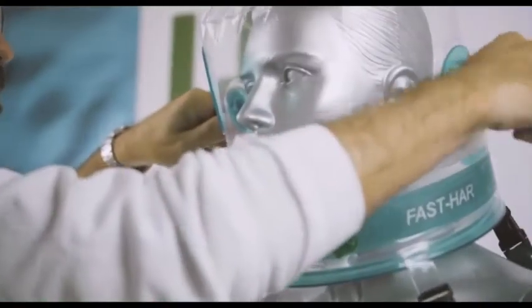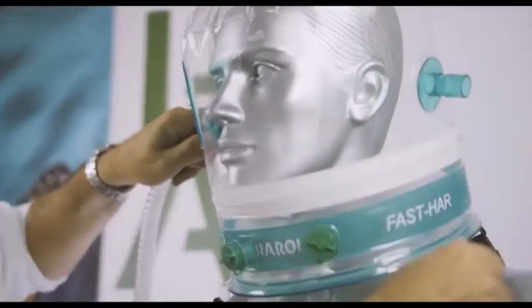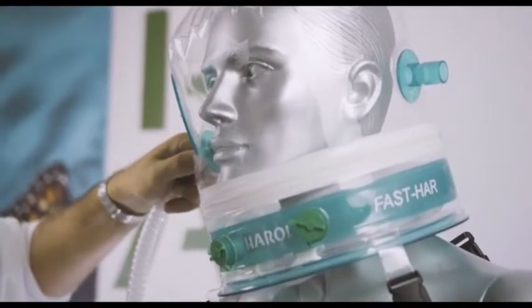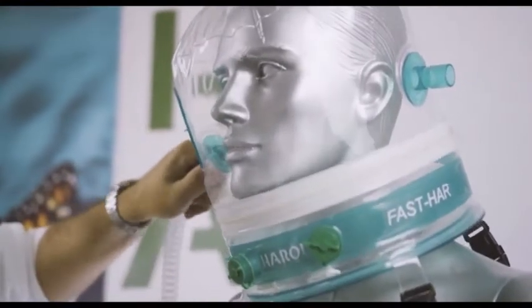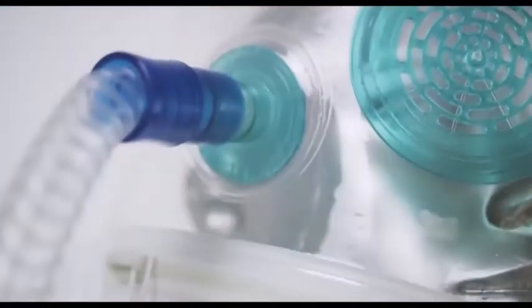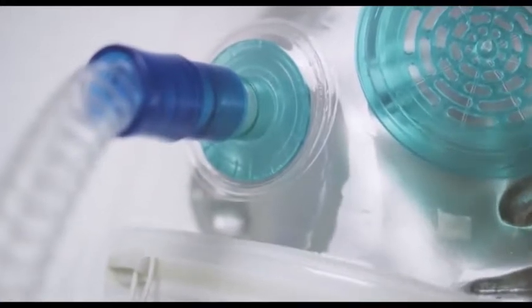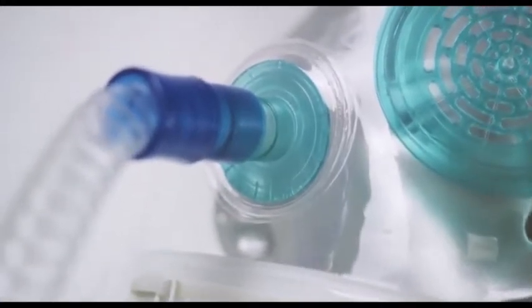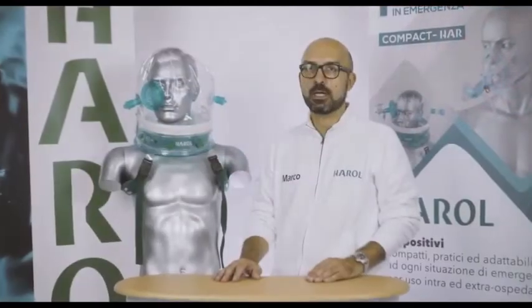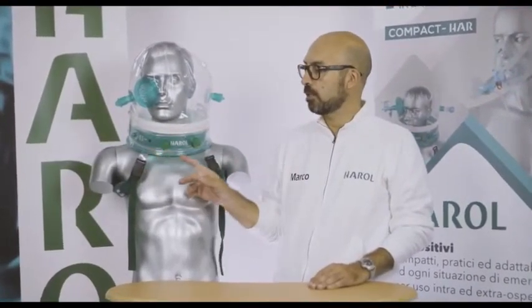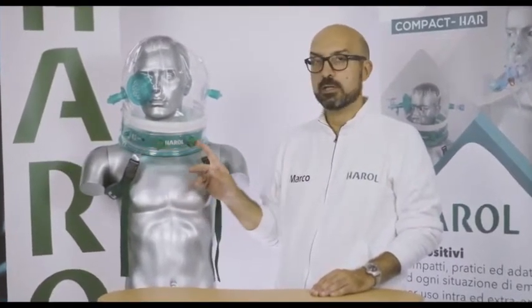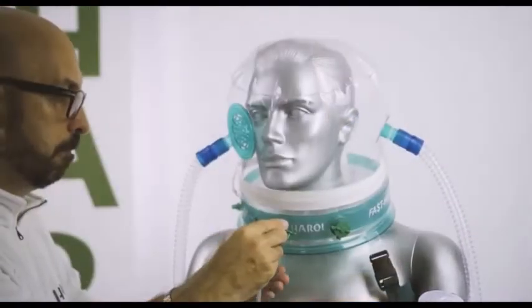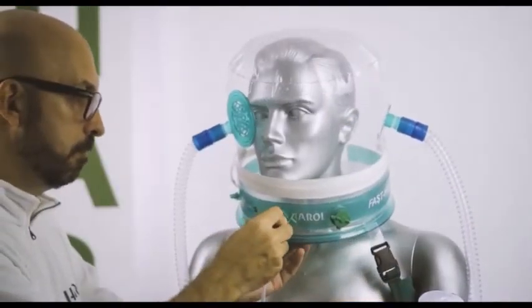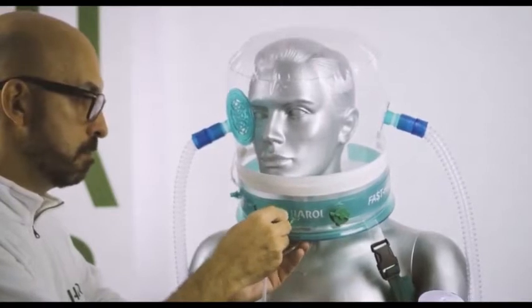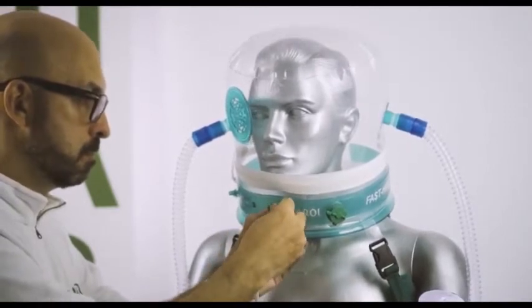On the sides of the tent, there are two symmetric connections, both 22mm male inlet and outlet, conforming to ISO standards. On the lower part of the tent, there are two additional leak-tight accesses for the introduction of nasogastric tubes or straws for liquid feeding. Through this access, it is also possible to ventilate with a Y-circuit and a catheter mount.